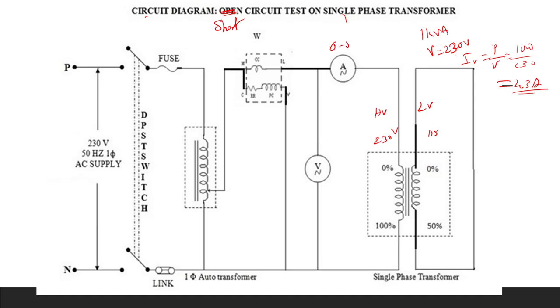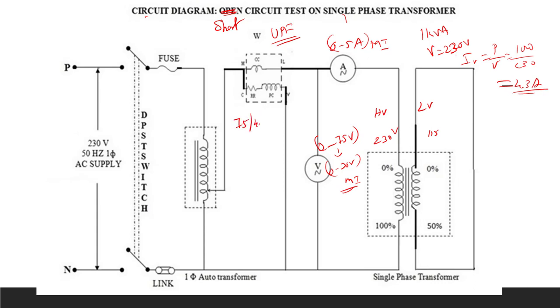Take an ammeter in the range of 0 to 5 amps MI since the rated current is 4.3 amps. For voltage, the short circuit voltage is 10 to 20 percent of rated, so fix a voltmeter of 0 to 75 volts or 0 to 30 volts MI. Since the current is maximum, use a unity power factor (UPF) wattmeter — 75 volt, 5 amp UPF wattmeter.